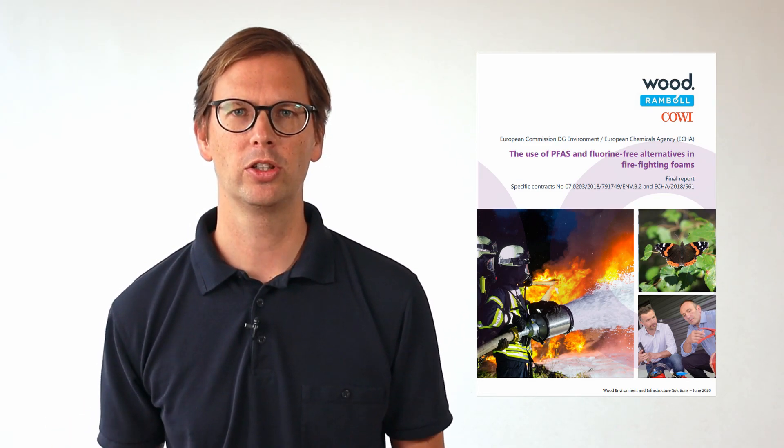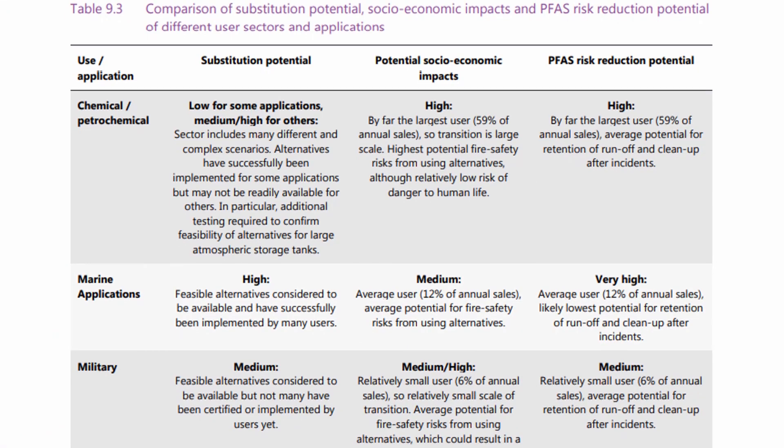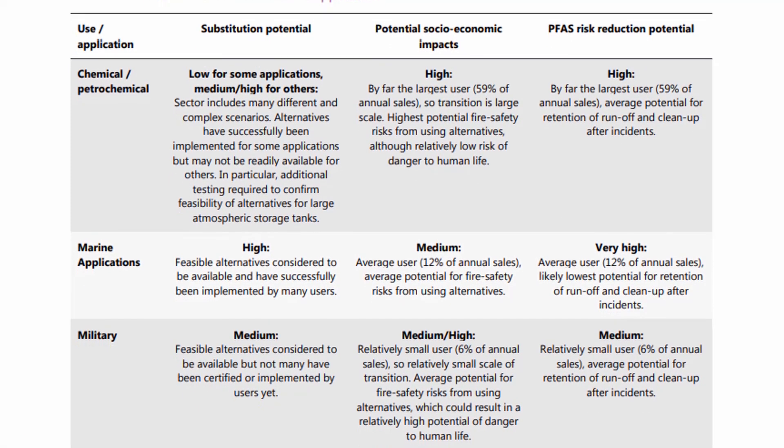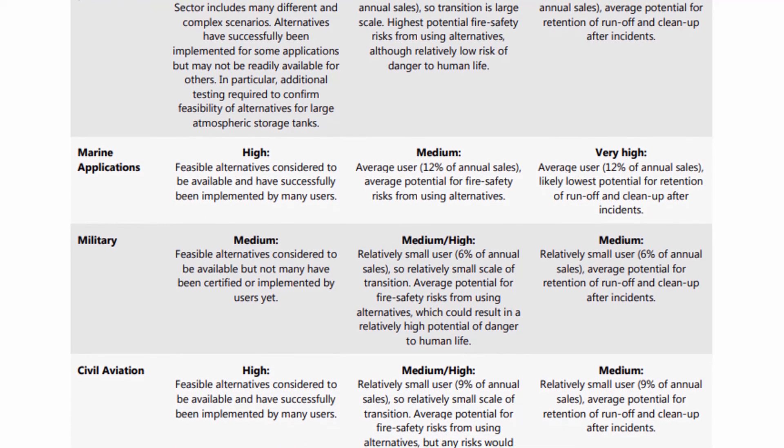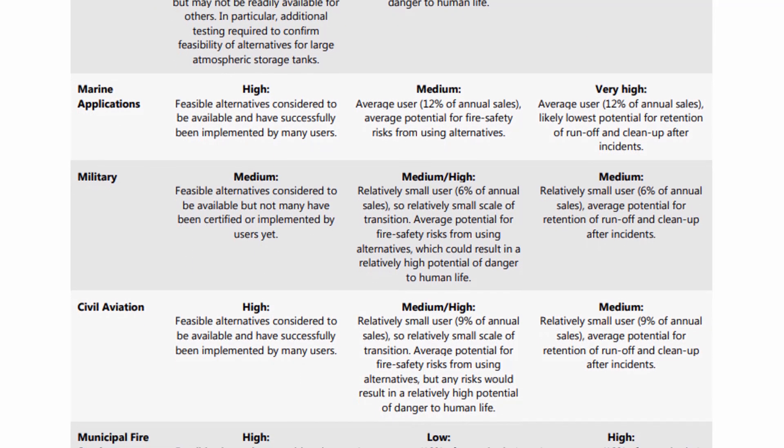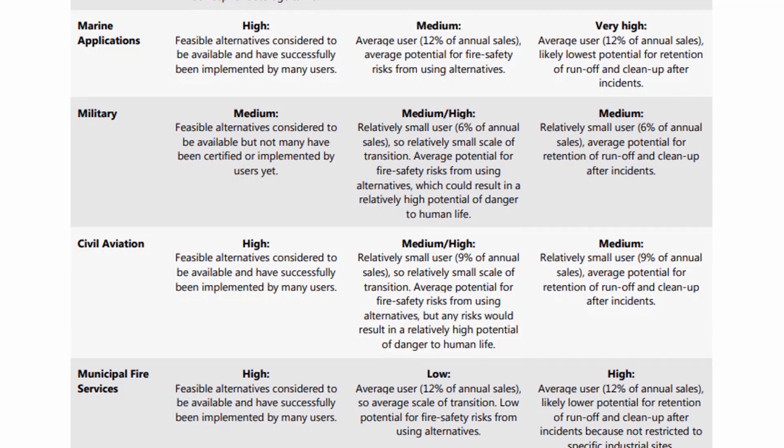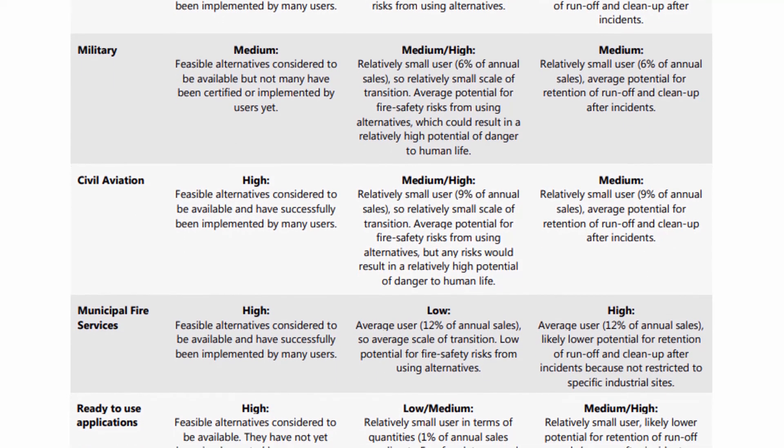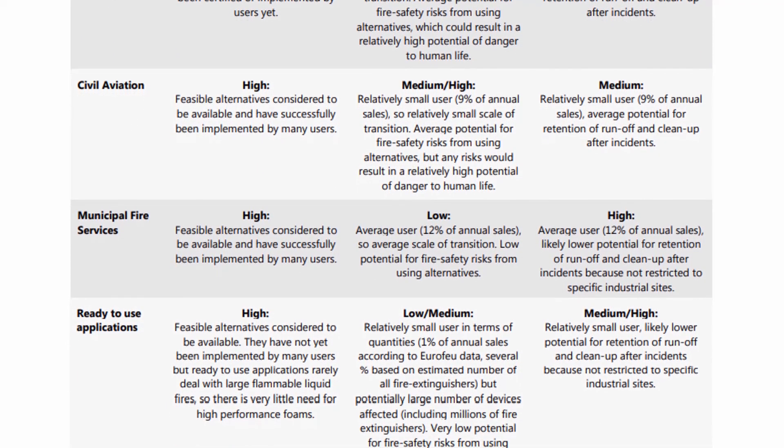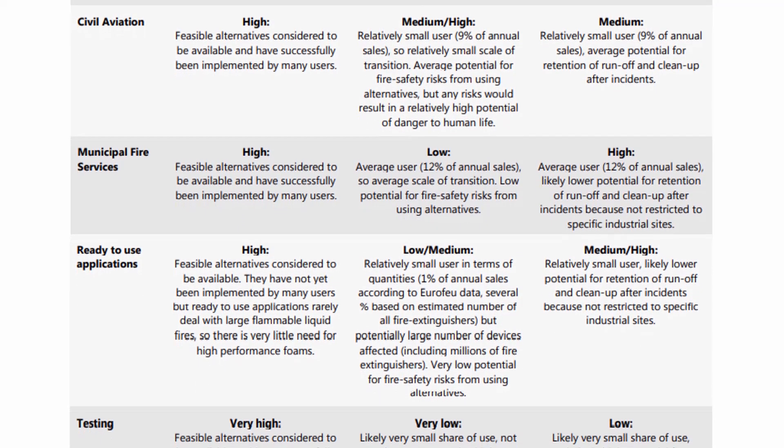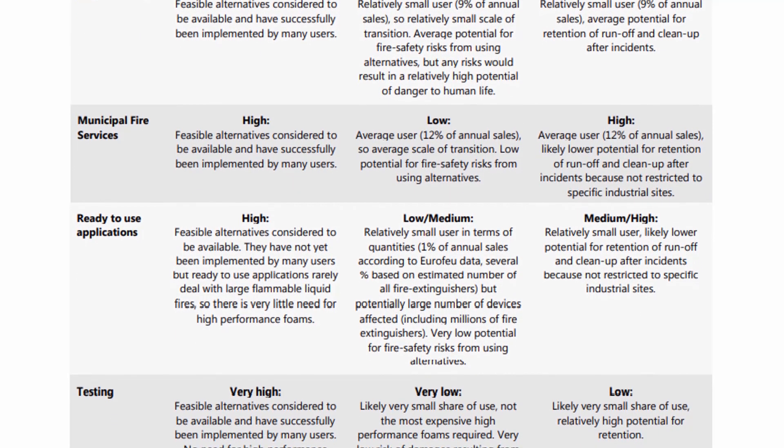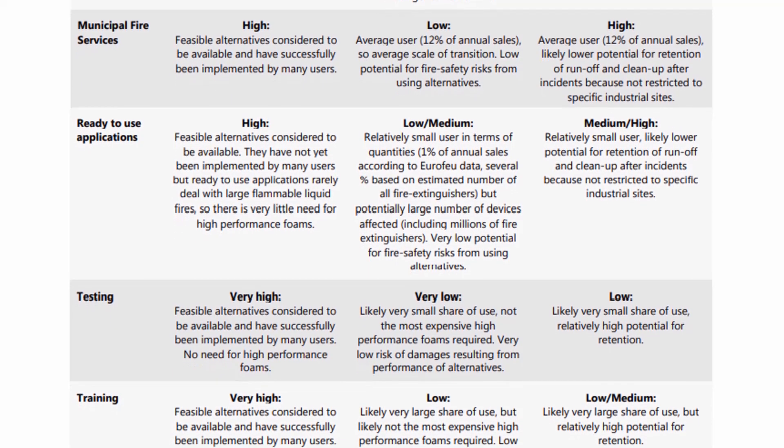In summary, the report recommends the restriction of PFAS in foam concentrates. But it also differentiates between various fields of applications, such as municipal fire brigades, the military, the chemical and petrochemical industry, or even training with foam. For these fields of application, the report also considers the effect on fire protection if fluorinated foams are banned. Tank fires are considered as the most critical scenario. It is also proposed to use different transition periods for different fields of application. They range from 3 to 10 years, although there is no transition time for training and testing with fluorinated foams.